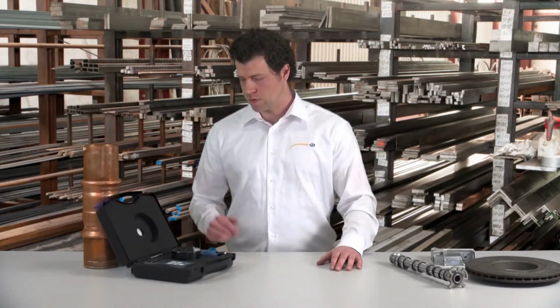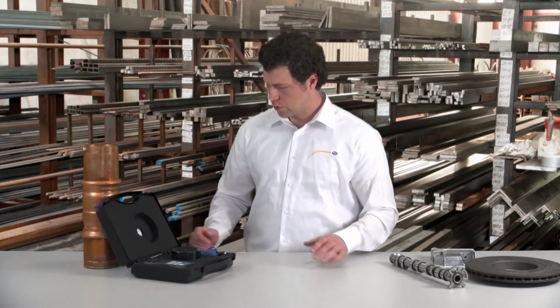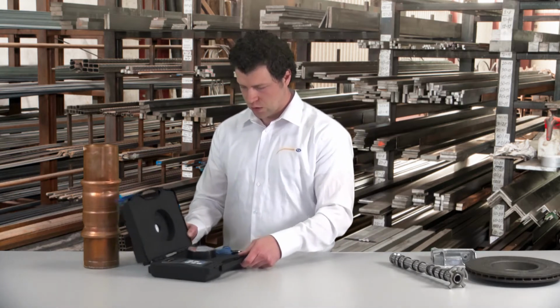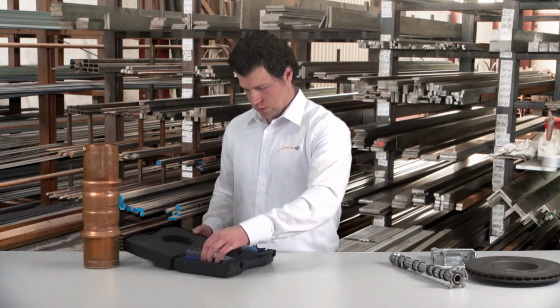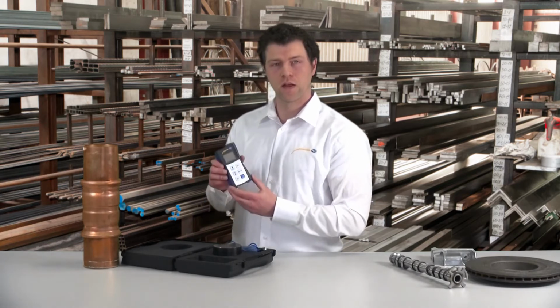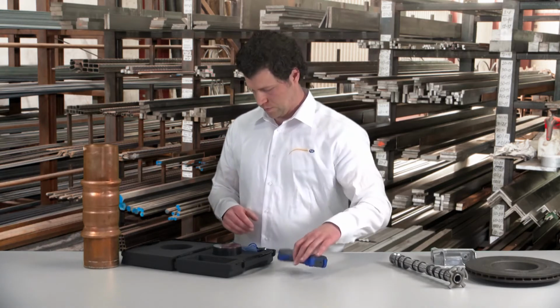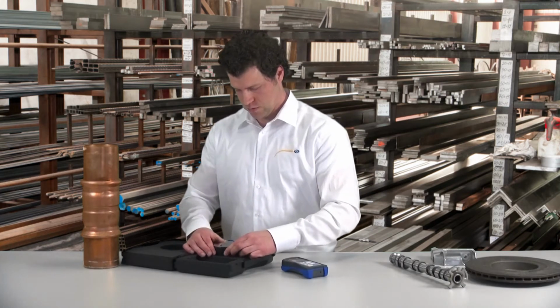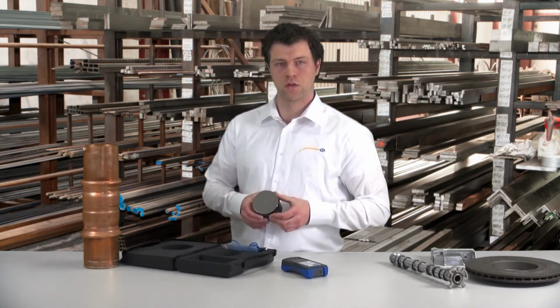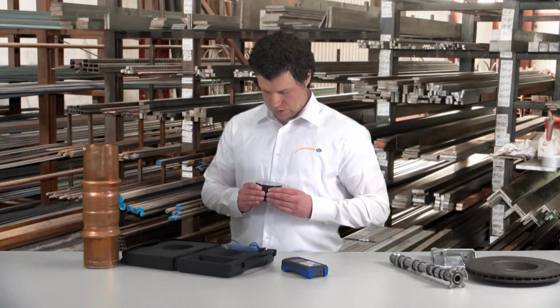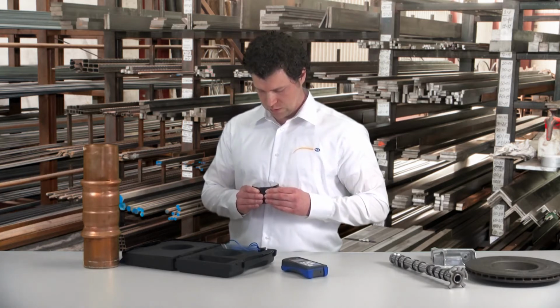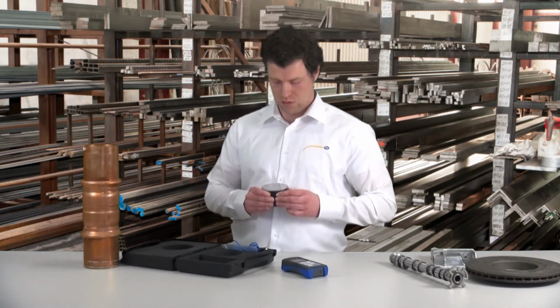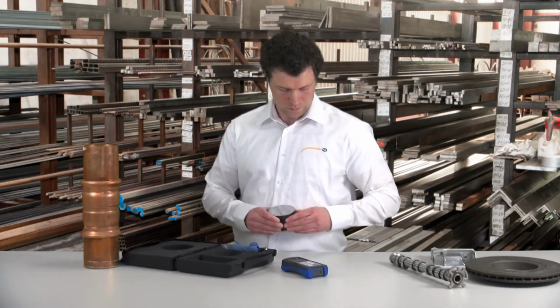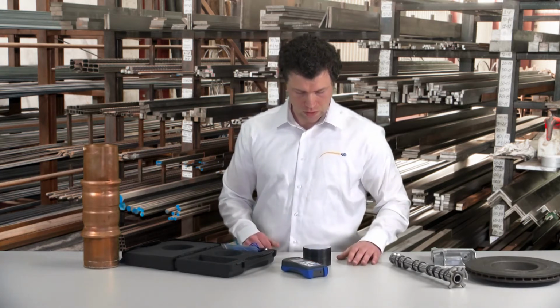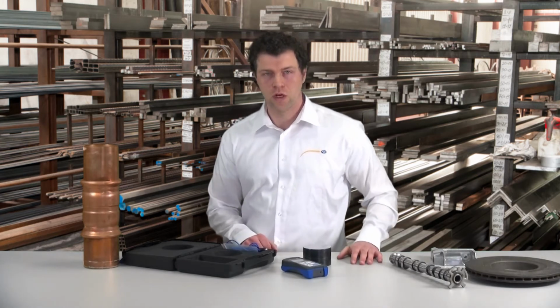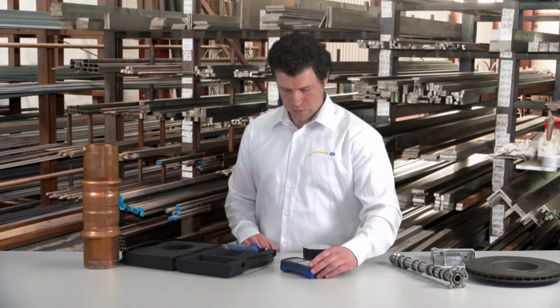We have the device here. We can have a look at the contents. To this belongs the display unit. Then we have a hardness comparing block. On this comparing block the hardness is engraved in Leeb. In this case it is 774. With this comparing block you can calibrate or adjust the device or just compare to see if the measuring exactness is still there.